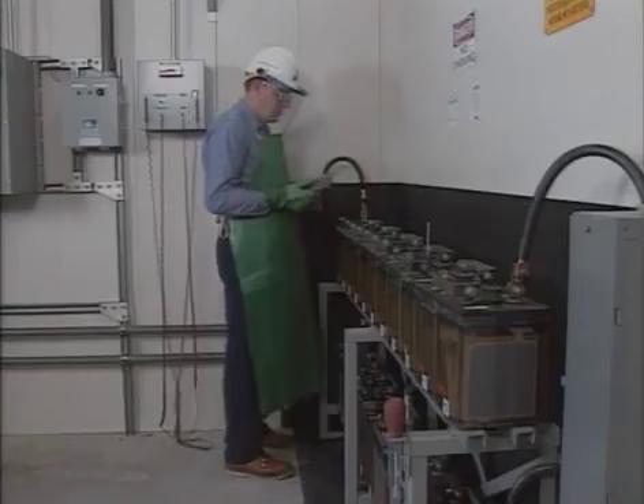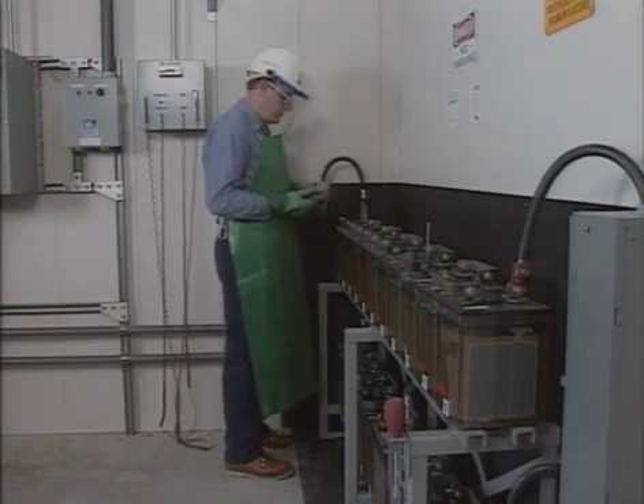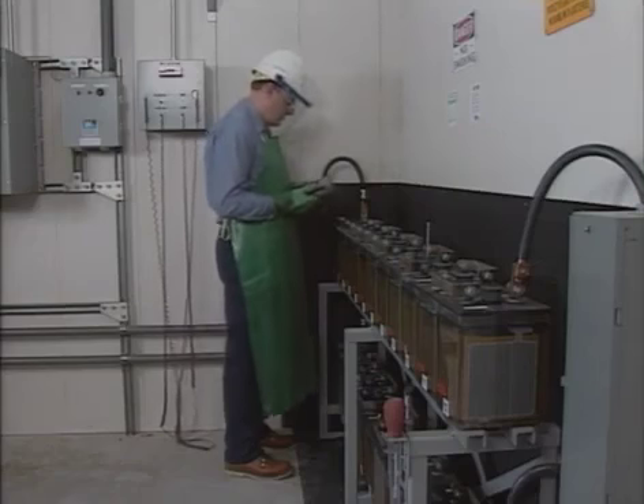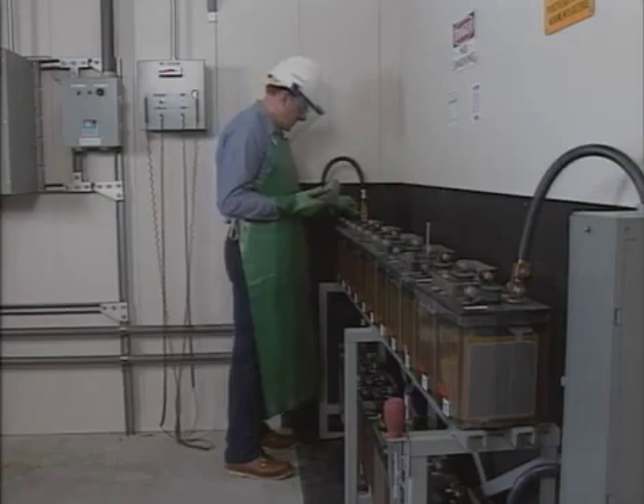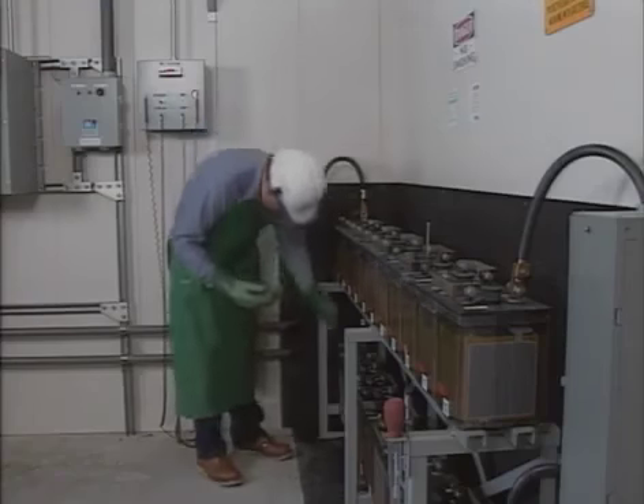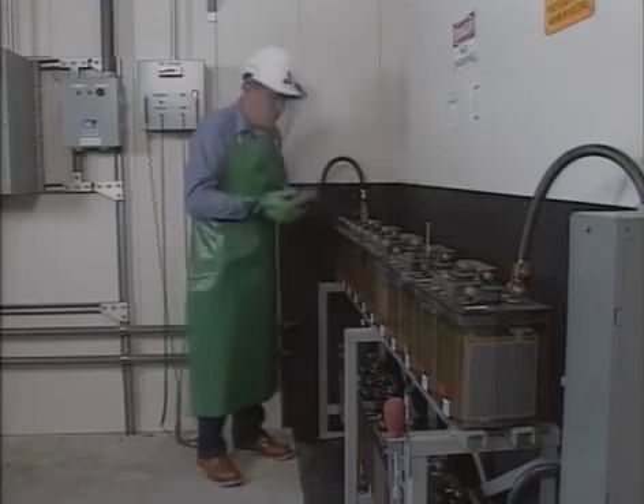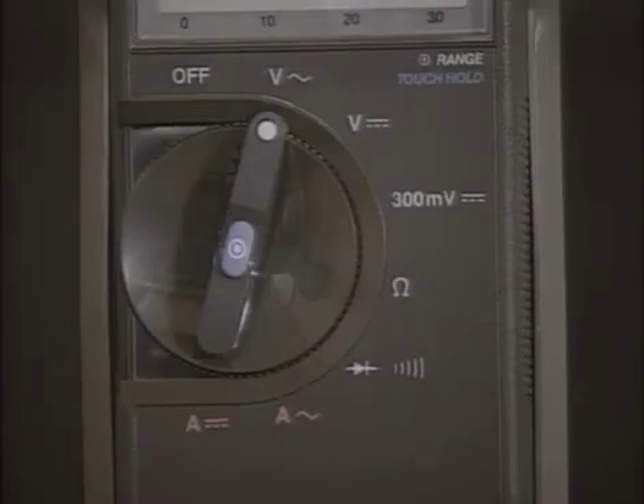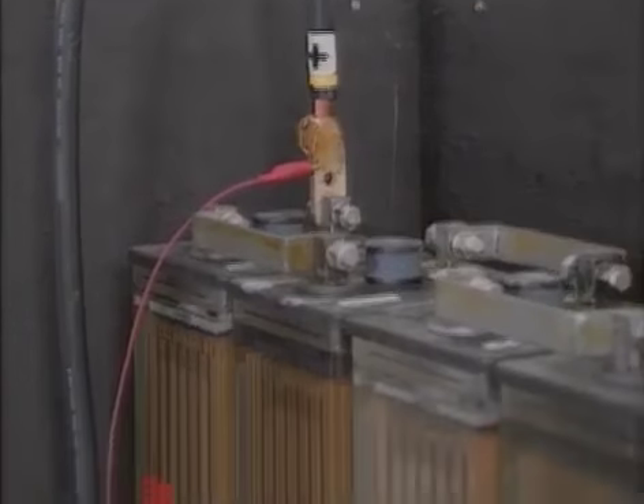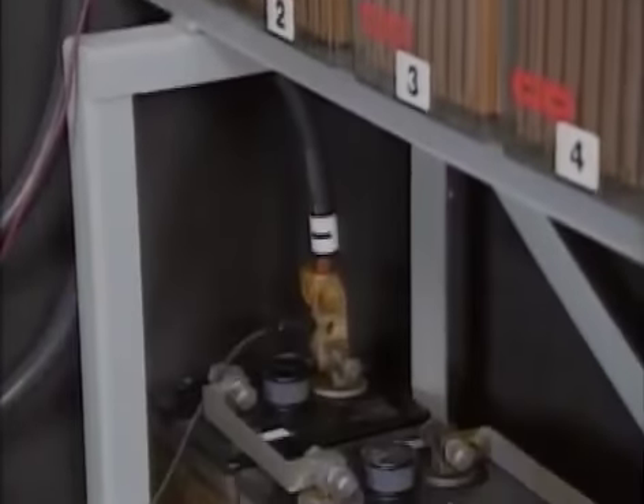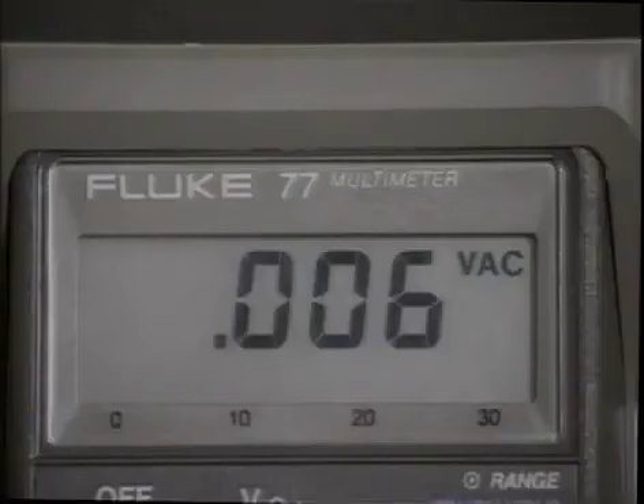On a periodic basis, it's a good practice to check for AC voltage at the battery. If a charger starts to go bad and loses its ability to convert AC to DC, it will show up at the battery. A meter, such as this digital volt-ohm-meter, can be used by setting it to measure AC voltage and placing the test probes across the terminals of the battery. The AC voltage reading here is within reason.